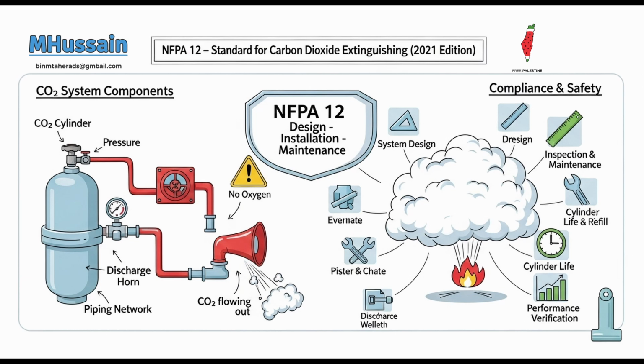High-pressure cylinders are rechargeable, storing liquid CO2 at ambient temperatures. High-pressure cylinders like welding gas. Similar concept, yes, which means the internal pressure fluctuates with the surrounding temperature. For example, it's around 850 psi, 5860 kPa, at 70 degrees F, 21 degrees C. Pressure changes with temperature. These cylinders must meet stringent U.S. DOT or Canadian Transport Commission requirements, reflecting the dangers of storing high-pressure gas.